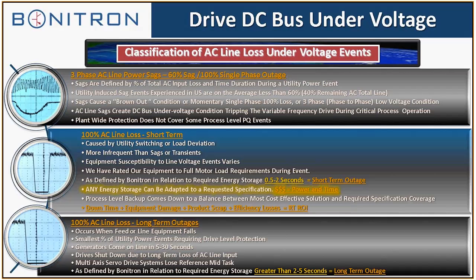So when discussing specification, Bonitron divides the ride-through or UPD products up into three different categories. Three-phase AC line power sags, and that's going to be the majority of your events. So usually in the United States, at least in the United States, we deal with a lot of sag events, 50–60% sags. As long as there's two other phases remaining and they have at least 70% and 70%, we can use a sag ride-through, a single unit you can put next to the drive. Sags are usually brownouts, or when the lights flicker, momentary condition.